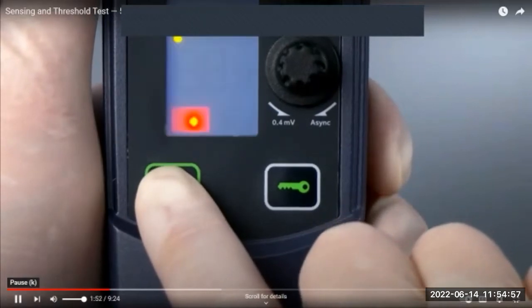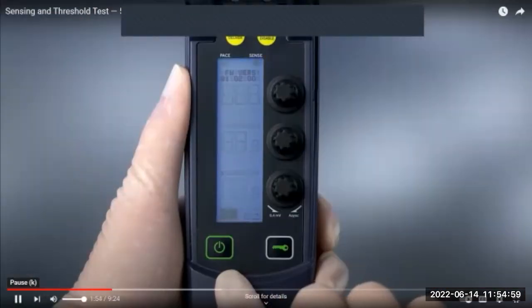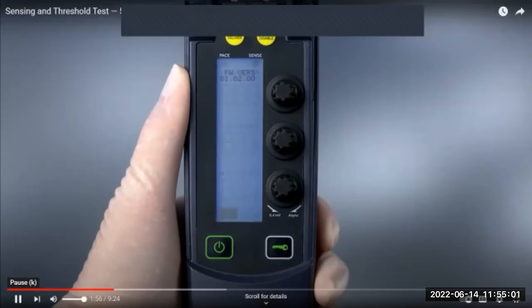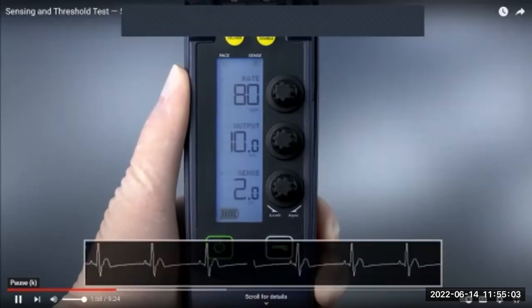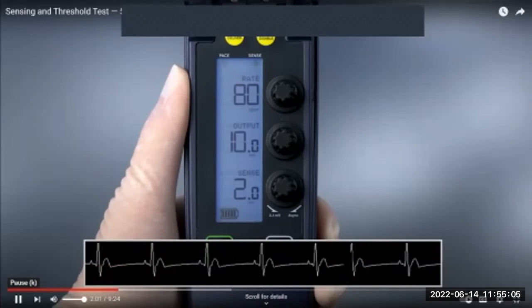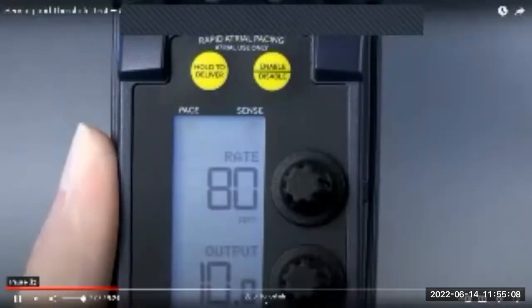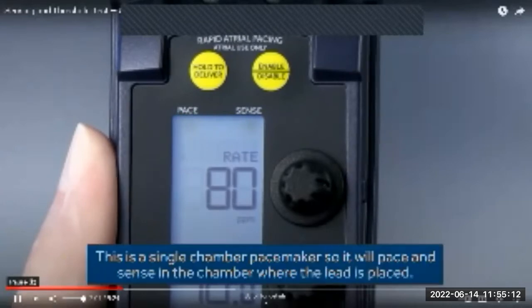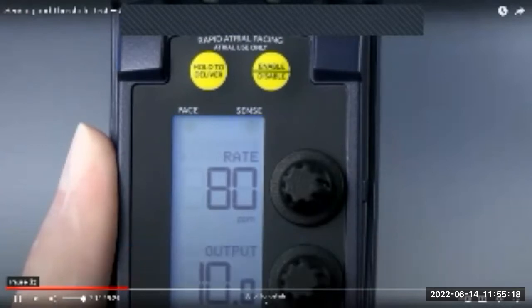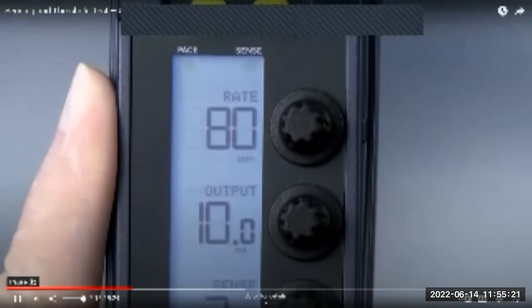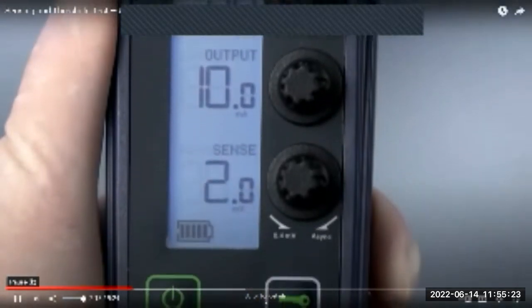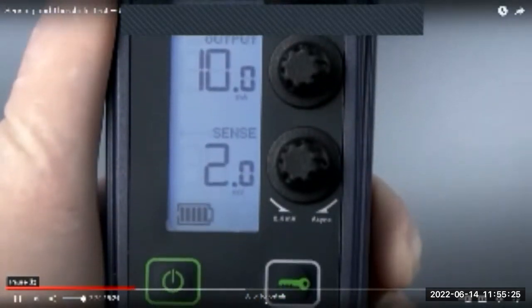To perform the sensing threshold test, first, turn on the temporary pacemaker without connecting it to the patient lead system. Ensure the patient is connected to an ECG you can monitor during the testing. When the temporary pacemaker is initially turned on, it will begin sensing and pacing in AAI or VVI mode with nominal values of a rate of 80 ppm, output of 10 milliamps, and sensitivity at 2 millivolts.